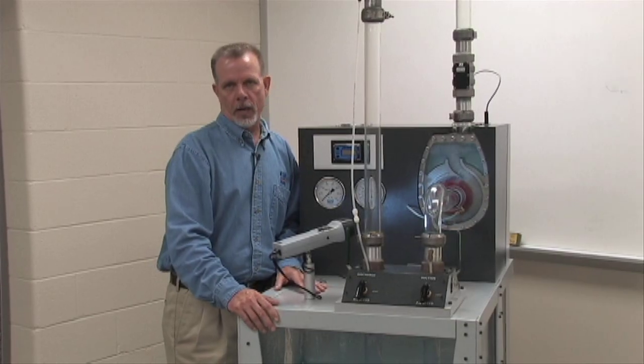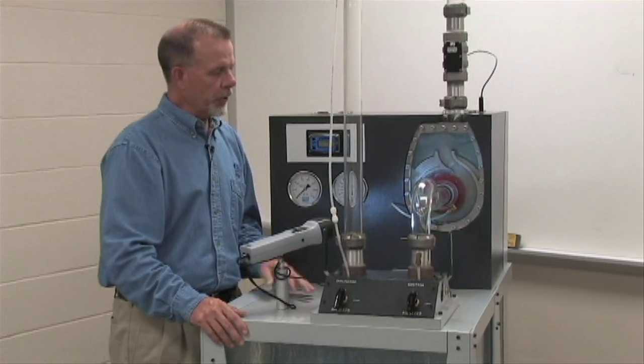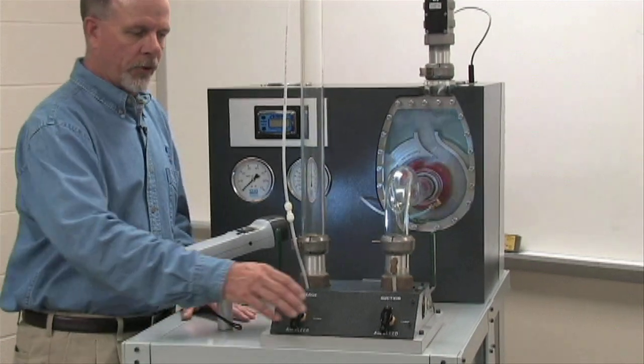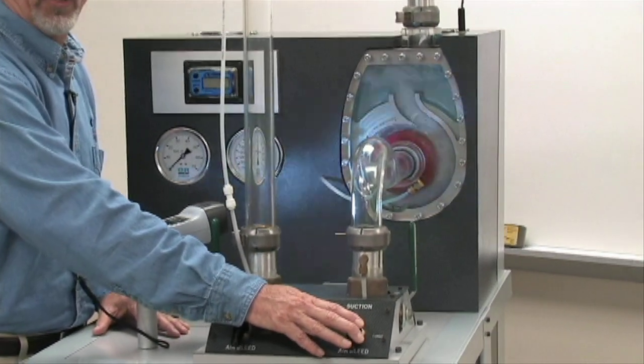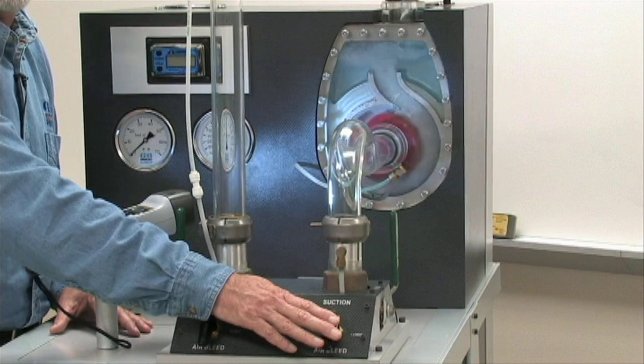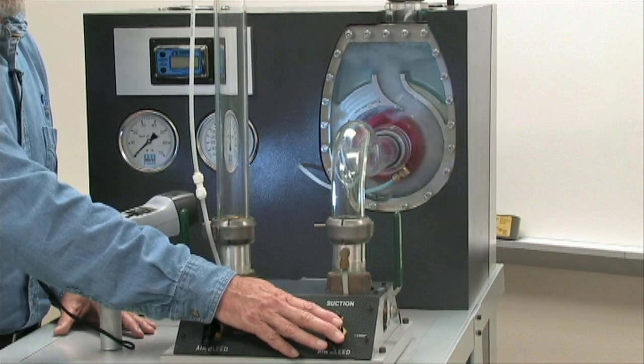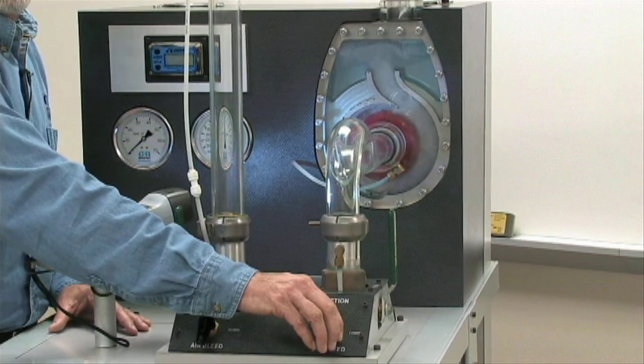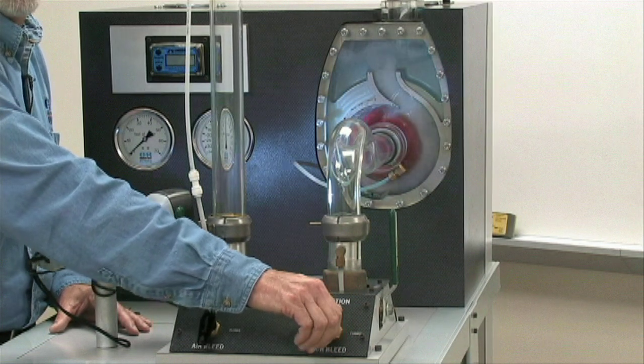One cause of failure to prime is an air leak. During the recirculation process, we have left open an air bleed valve allowing atmospheric pressure into the suction line, simulating an air leak. By closing this valve, we now have a suction line capable of pulling a vacuum.